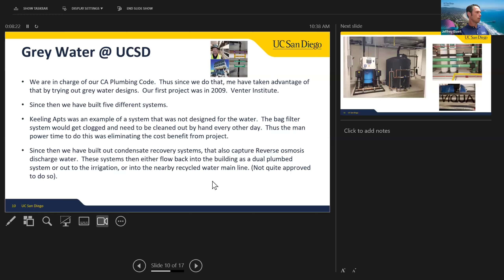So now we've built out a few more condensate recovery systems. Since we're by the beach we have high humidity and a lot of laboratories, so we're already drying out the buildings with the air handler units. We designed it to intercept the floor sinks where the HVAC units discharge, run it to a large tank, put it through a little treatment, and then either inject it out to irrigation, or what we've started trying to do, inject it into our 12-inch recycled water main line on campus.